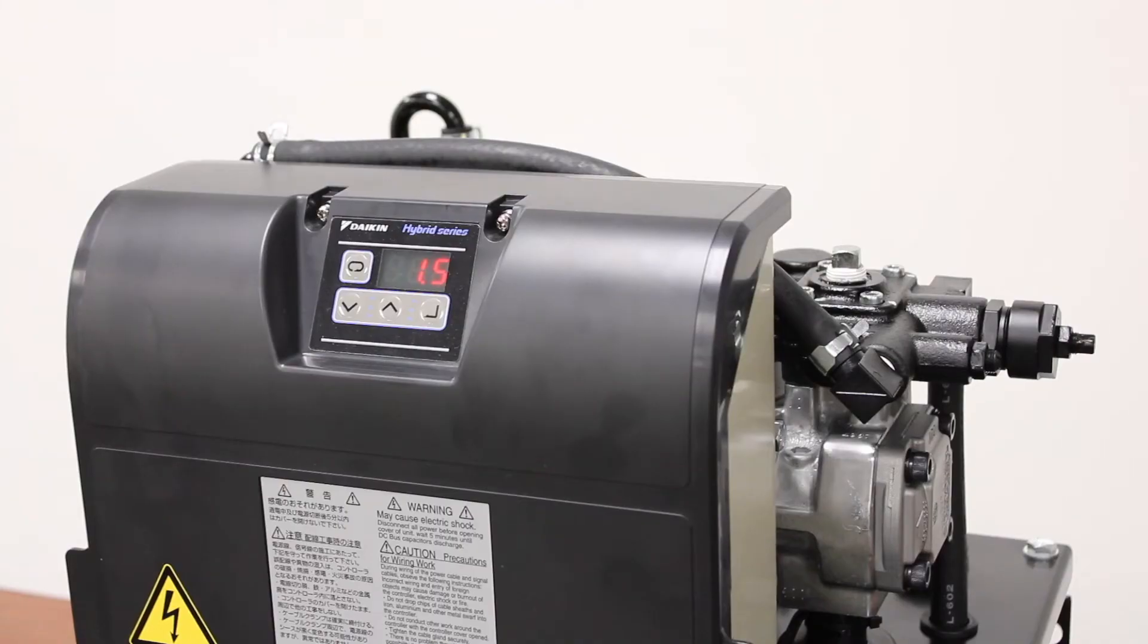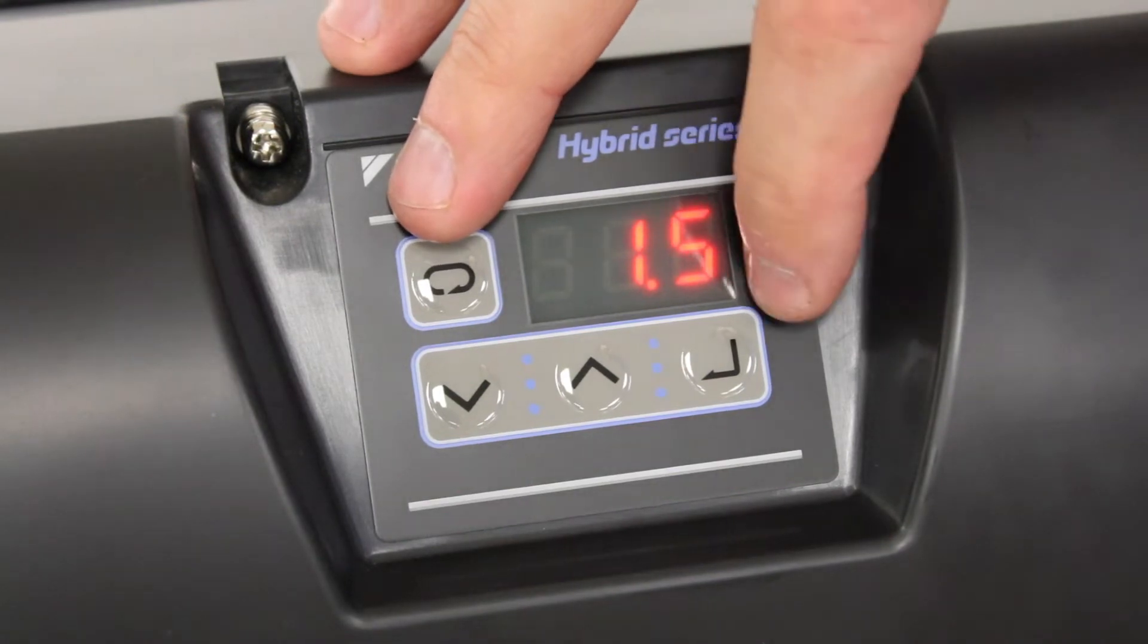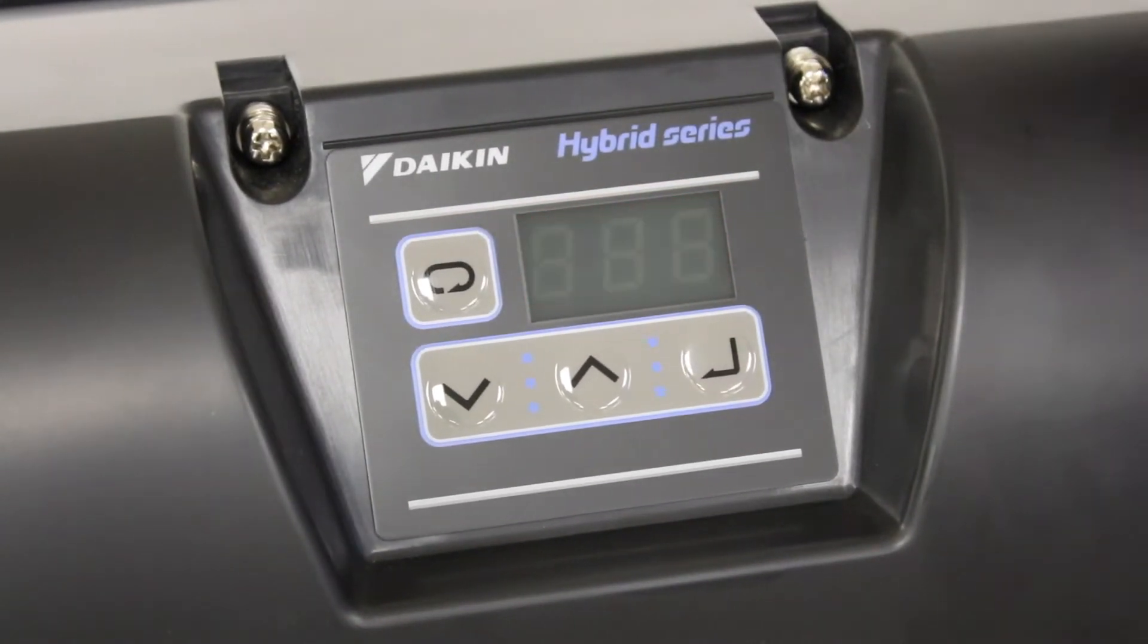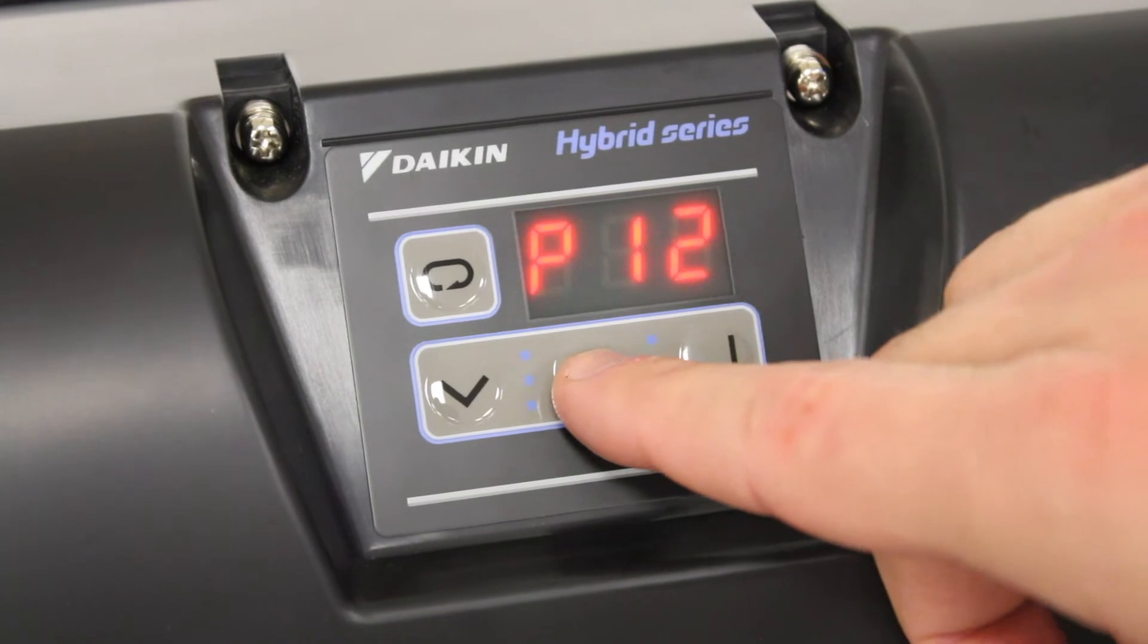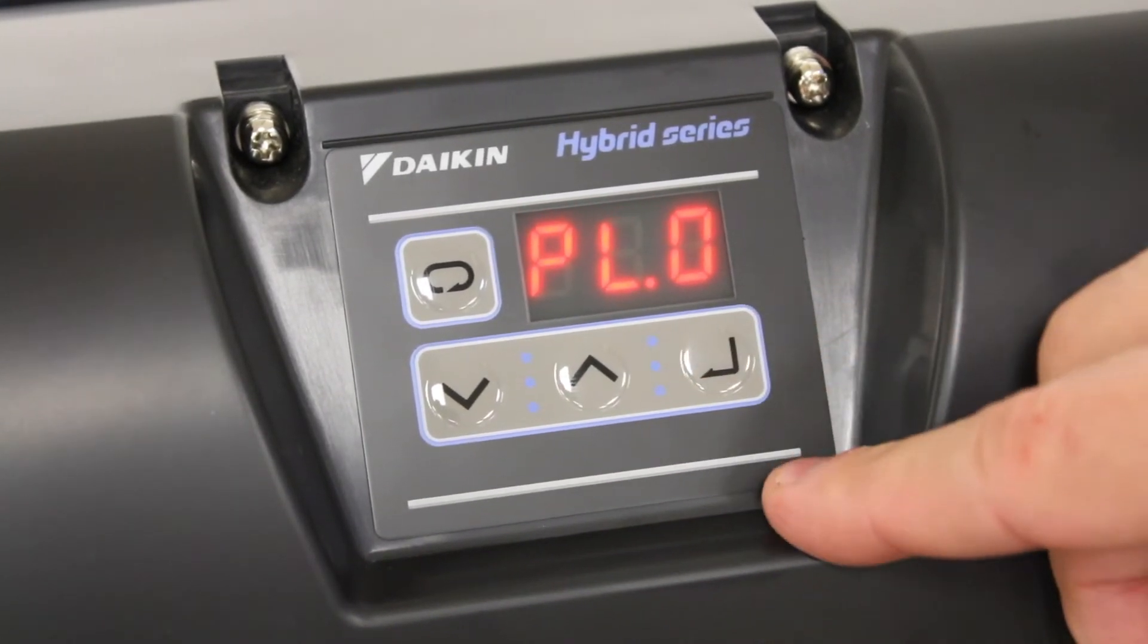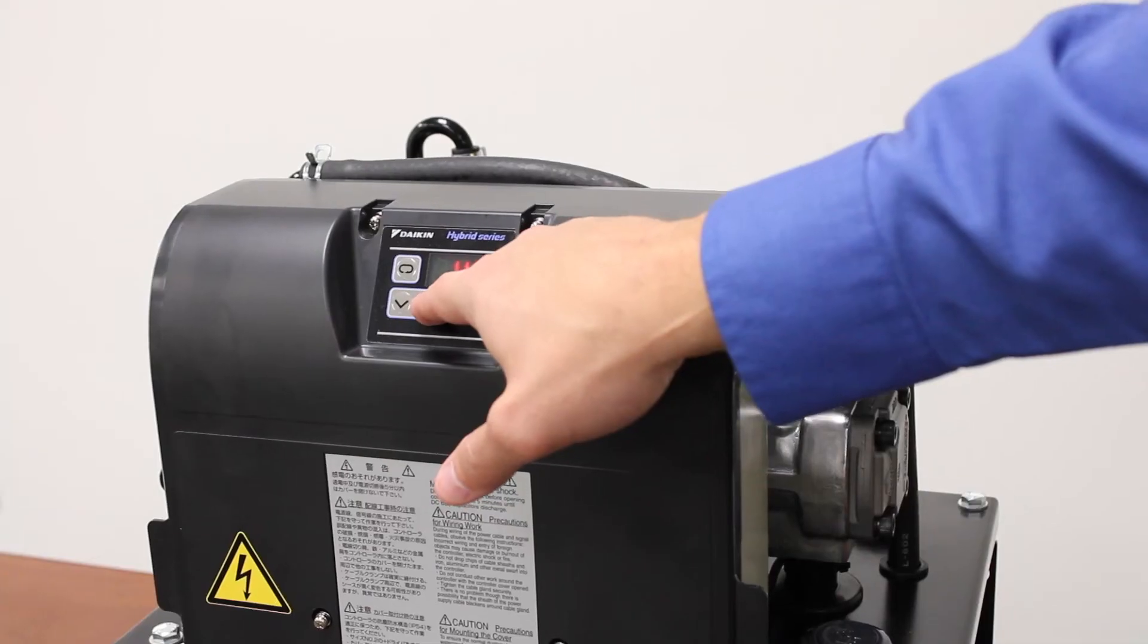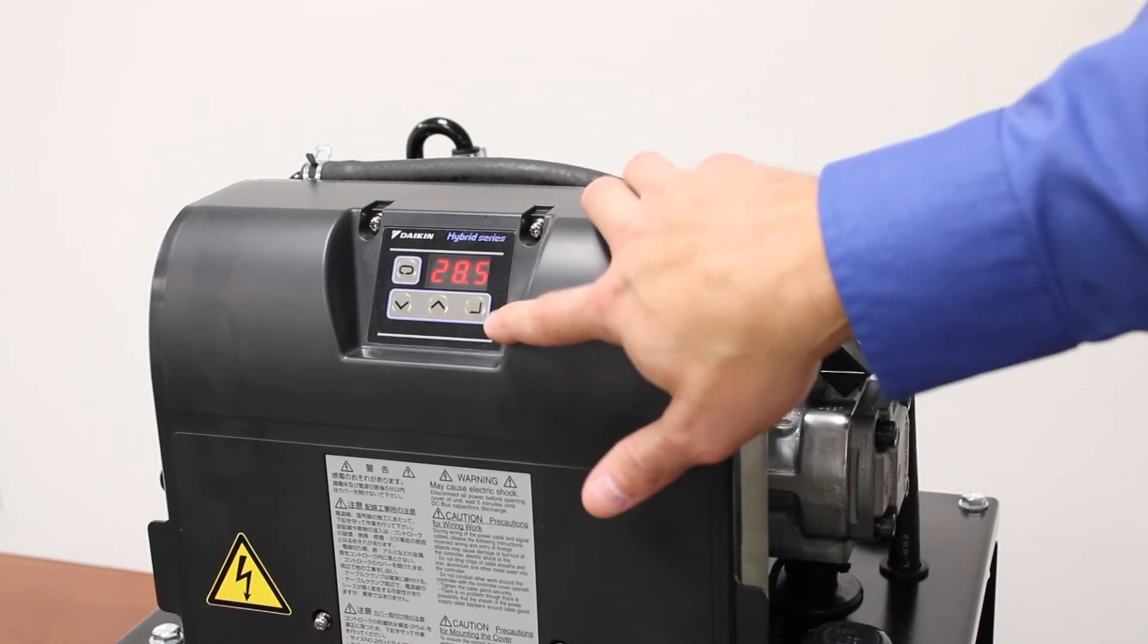To set system pressure, we need to get into parameter mode on the keypad. To get to parameter mode, we're going to hold down the menu and the return key simultaneously for three seconds until it flashes P00 on our display. From there, we use the up arrow to scroll up to parameter P13 and hit enter. You'll see the readout PL0 and our current pressure setting which is 1.5. You can adjust that by using your up and down arrows. Once you've reached your set point, hit enter to save it.